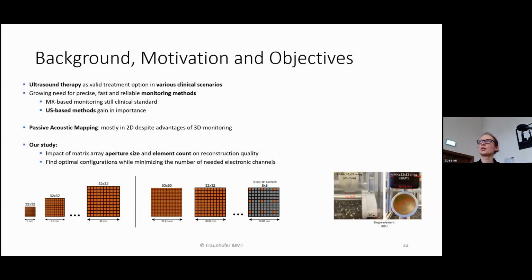MR-based monitoring is still the clinical standard, but ultrasound-based methods gain in importance as they are able to overcome several limitations of MRI. And one of these ultrasound-based methods is the so-called passive acoustic mapping. This works for monitoring cavitation bubbles during treatment. Despite the potential of 3D monitoring in terms of safety, most implementations remain in the 2D regime, for example, due to hardware requirements.